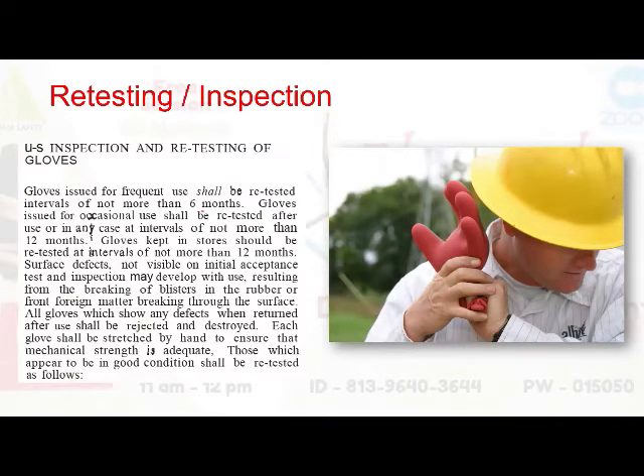Our EB rule says, and Indian standard also says, that every 6 months once we have to retest the electrical gloves, or yearly once we have to replace it, checking which condition the gloves are in. This is per IS standard 4770: every 6 months we have to test, and yearly once we need to replace.